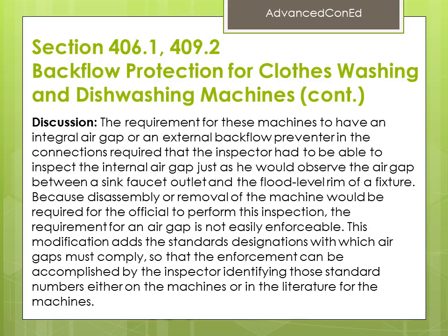Because disassembly or removal of the machine would be required for the official to perform this inspection, the requirement for an air gap is not easily enforceable. This modification adds the standards designation with which air gaps must comply, so that the enforcement can be accomplished by the inspector identifying those standard numbers either on the machines or in the literature for the machines.